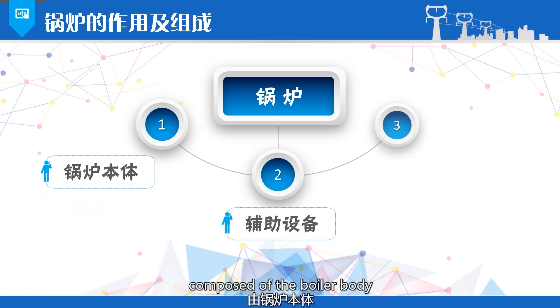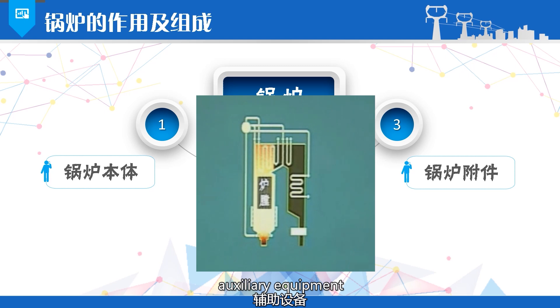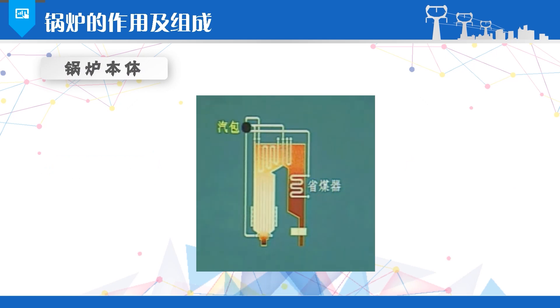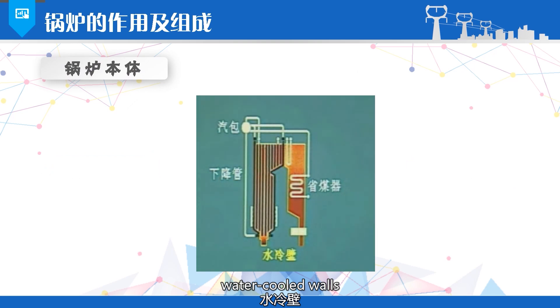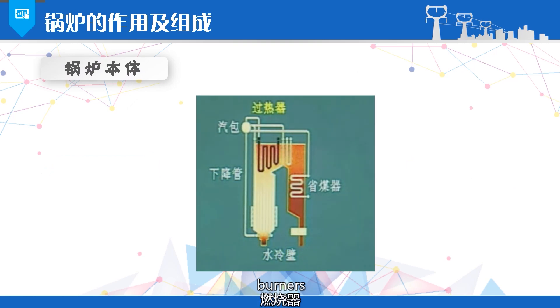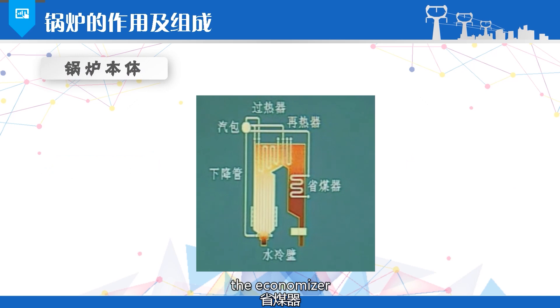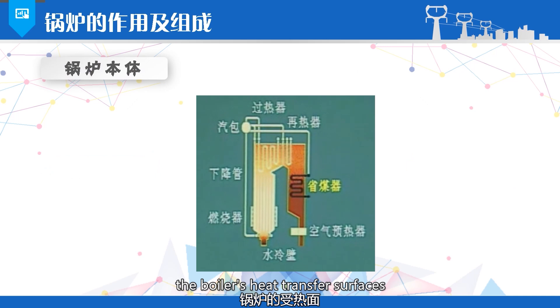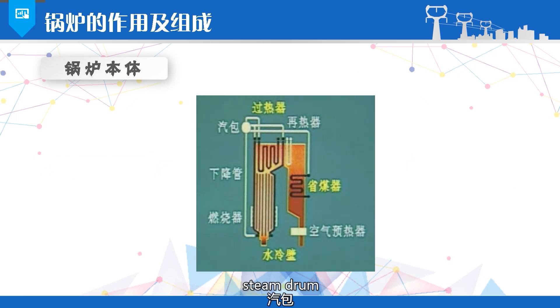Boilers are generally composed of the boiler body, auxiliary equipment, and boiler accessories. The boiler body is the main component of the boiler. It consists of the furnace, flue ducts, economizer, steam drum, downcomer tubes, water-cooled walls, superheater, reheater, burners, and air preheater, among others. Among these, the economizer, water-cooled walls, superheater, reheater, and air preheater are referred to as the boiler's heat transfer surfaces.